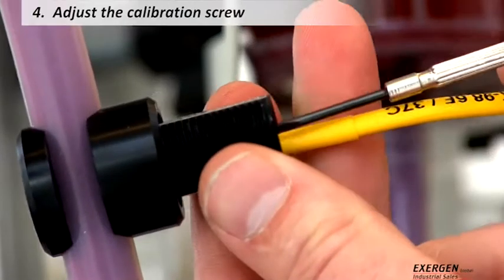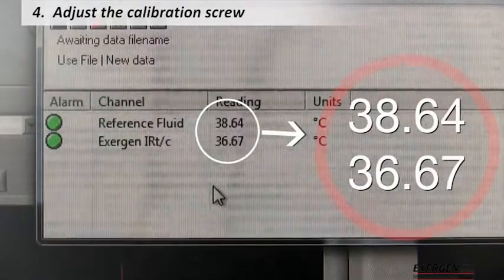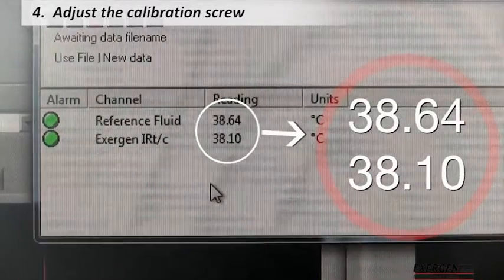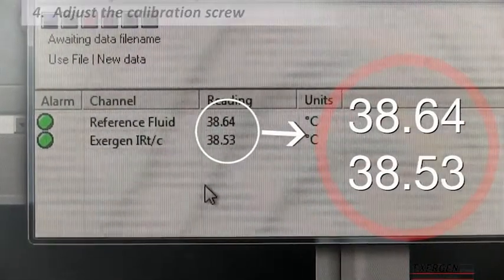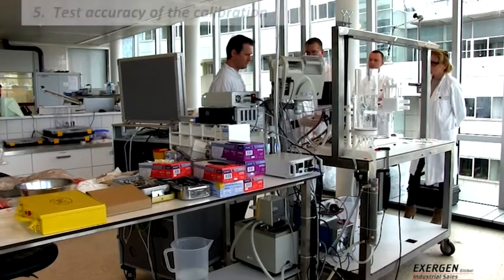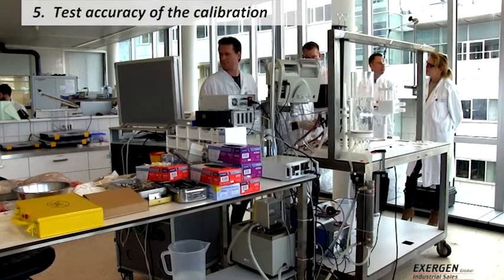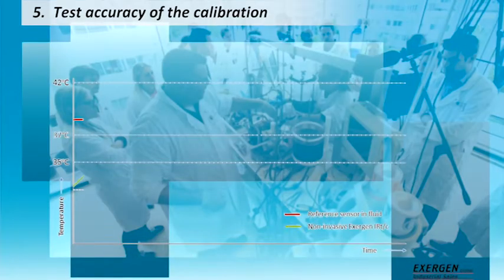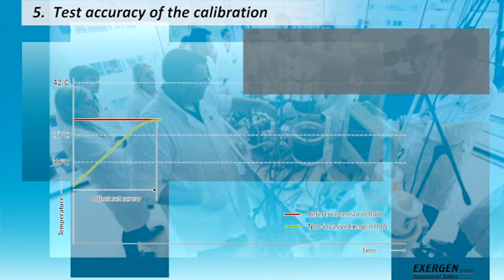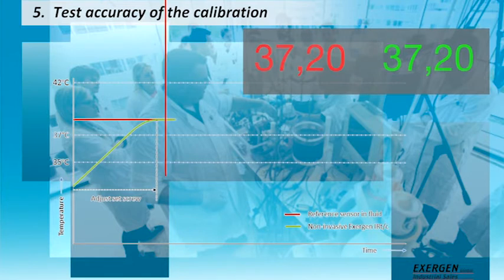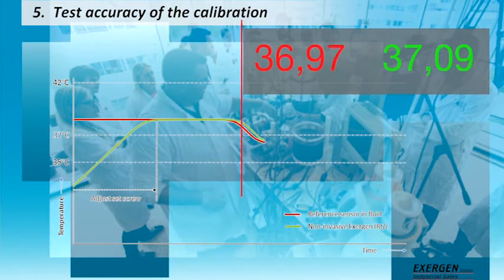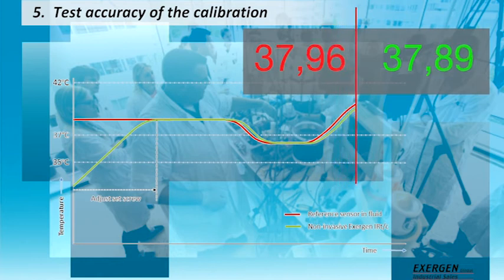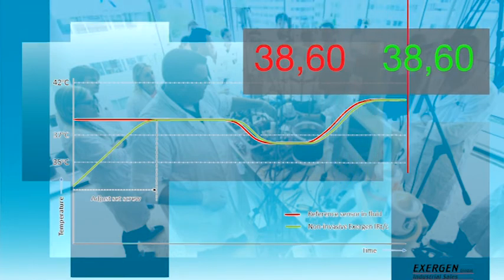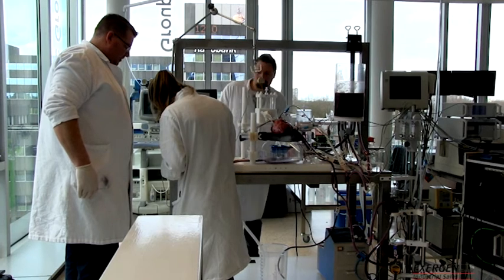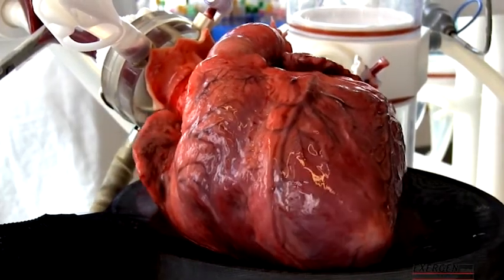Step 4. Adjust the calibration screw until the IRTC reading matches the reference fluid reading. Step 5. Test if the calibration is accurate over the temperature range of interest by varying the fluid temperature. In this case between 35 and 42 degrees Celsius. If the sensor follows the reference sensor accurately, the calibration is successful. Possibly, some fine-tuning of the calibration screw is required to increase accuracy.